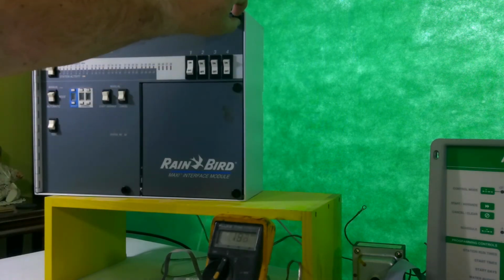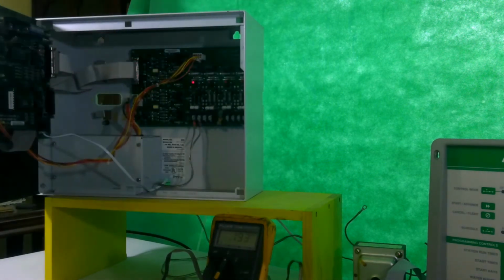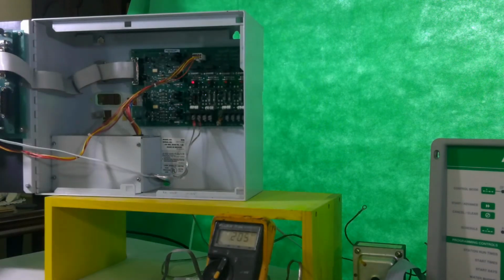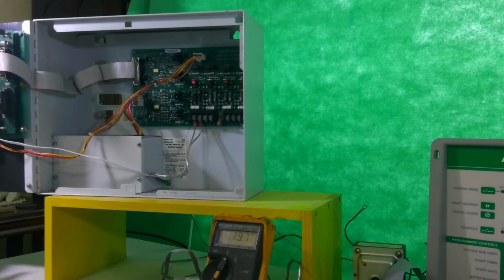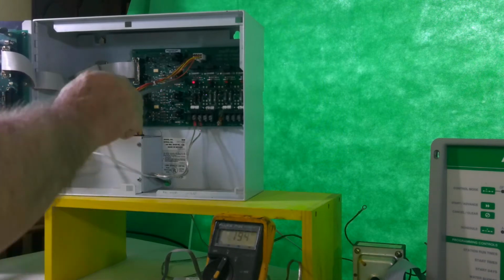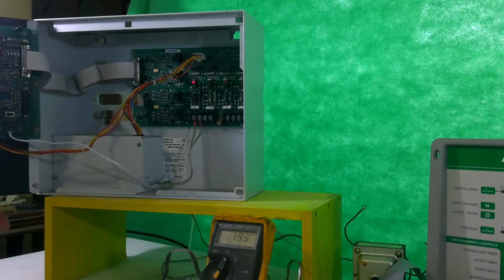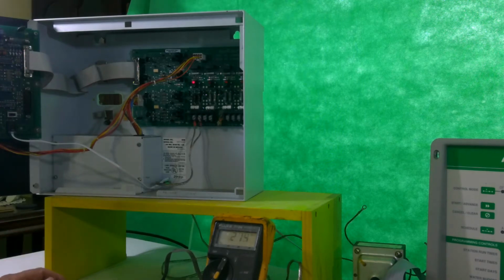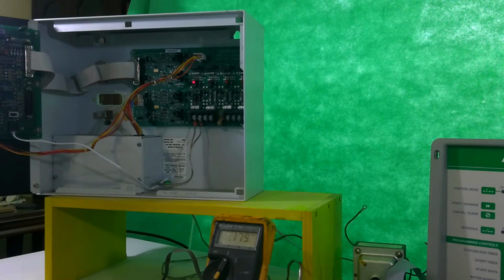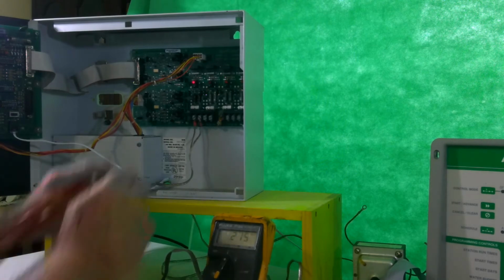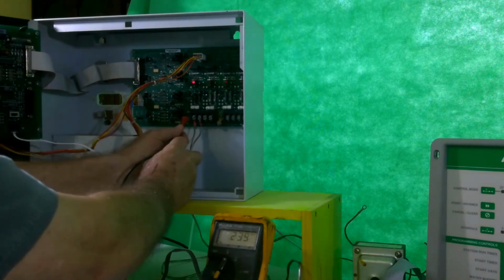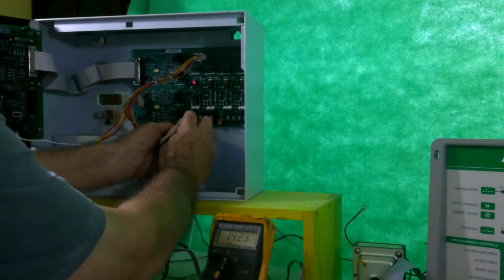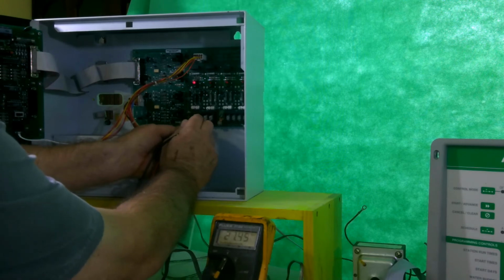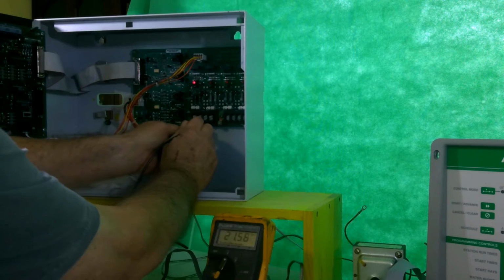Now I'm going to open the panel and check inside. And you'll notice that inside the unit there's an output board, and it has a flashing light right here. That's it, that it's sending out a signal. And we want to check that signal, and we do that by taking the volt-ohm meter on AC voltage, and we put one probe of our meter on one of the output screws and the other on the other output screw, and it shows us 21, 22 varying volts, and it should vary because it's a sine wave that's going out.